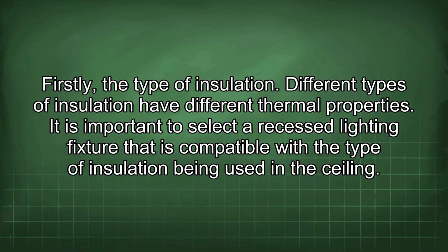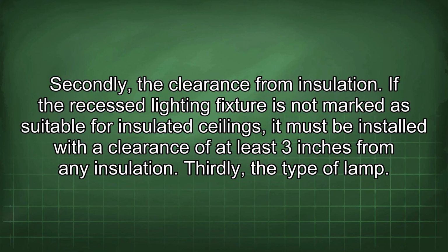Firstly, the type of insulation. Different types of insulation have different thermal properties. It is important to select a recessed lighting fixture that is compatible with the type of insulation being used in the ceiling. Secondly, the clearance from insulation. If the recessed lighting fixture is not marked as suitable for insulated ceilings, it must be installed with a clearance of at least 3 inches from any insulation.